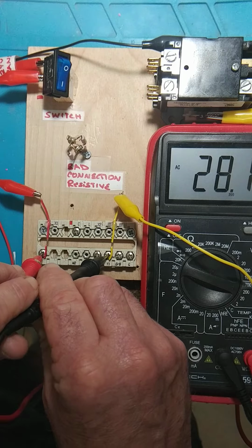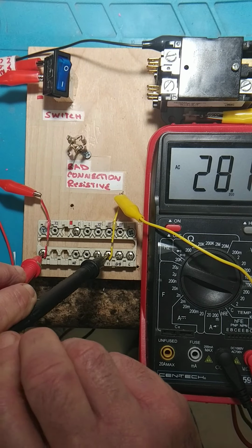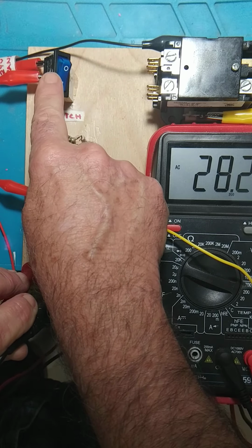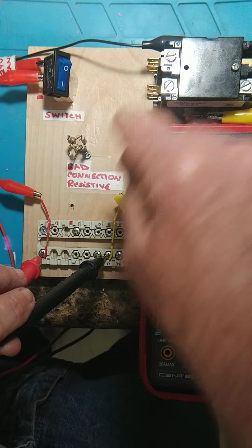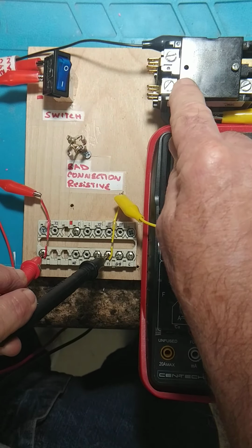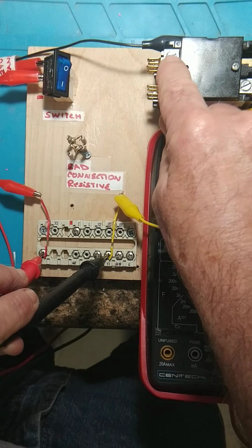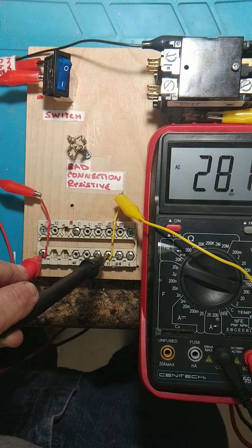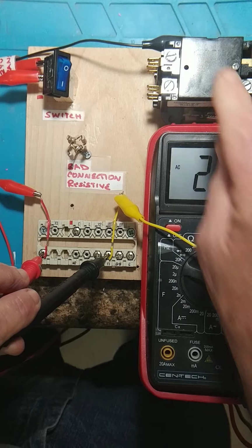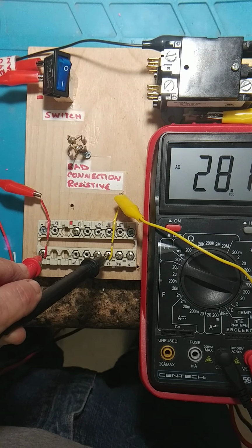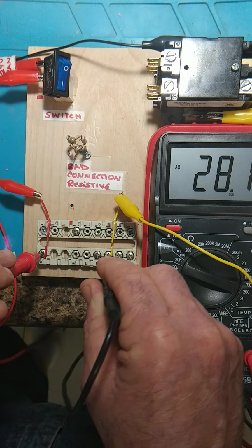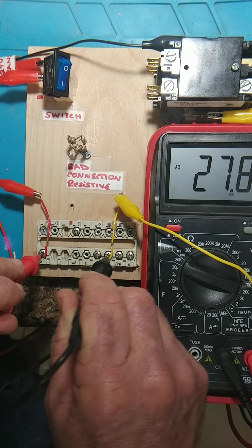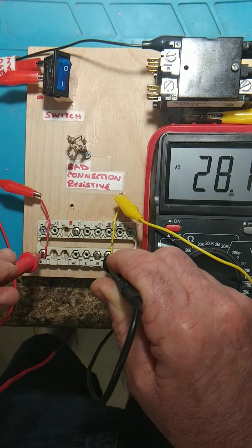And what this is telling me, when I take the thermostat off the wall and I'm checking, is I've got R coming to the R connection, so it's not off on the float switch. My wiring, common and my Y going to my compressor contactor, are good as far as there's continuity, and the coil of my contactor is good because there is continuity. So this is basically checking continuity using voltage. Okay. Now, this circuit's open, there's no current flow.